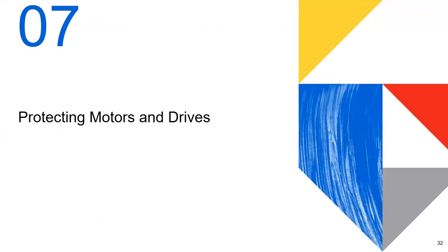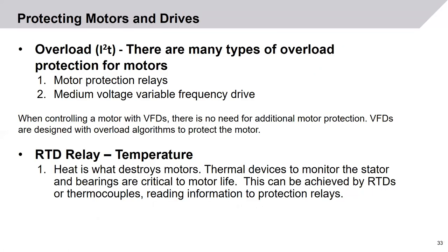Protecting motors and drives. Overload I²T: there are many types of overload protections for motors. When controlling a motor with a variable frequency drive, there is no need for additional motor protection, as variable frequency drives are designed with overload algorithms to protect the motor. RTD relays: heat is what destroys motors — thermal devices to monitor the stator and bearings are critical to motor life. This can be achieved by RTDs or thermocouples reading information to protection relays.